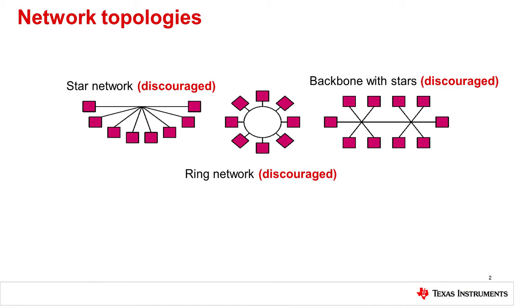Three common topologies which have disadvantages are the star network, ring network, and the backbone with star network. The star and backbone with star networks are discouraged because they purposely extend the stub length from the main transmission line. The ring network is discouraged because reflections from nearby connection points are more likely to degrade signal integrity at the intended receiver and may also reflect back into the transmitter. If any of these topologies must be used, the data rate should be drastically reduced to ensure reliable communication.